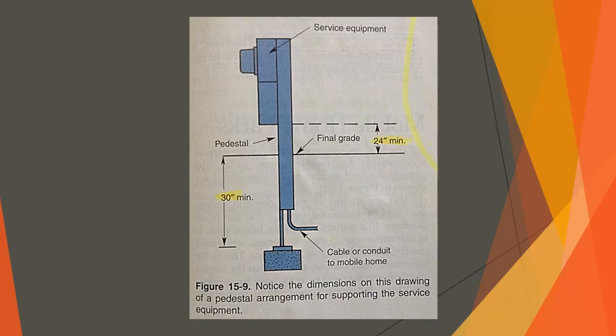The service lateral. For a lateral installation, that means underground, the mobile home must be fitted with a metal or rigid non-metal raceway that connects to the distribution panel inside the unit and extends to the underside of the chassis. The raceway must have a provision for attaching a junction box. The manufacturer may or may not have provided the raceway with the conductors. Refer to NEC section 550.10(B).